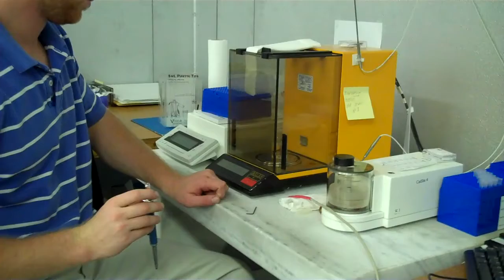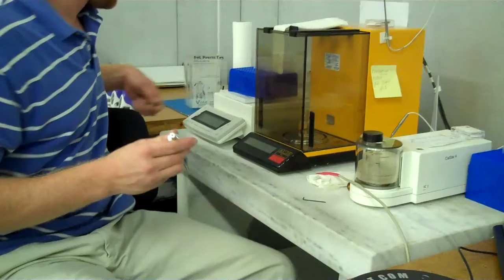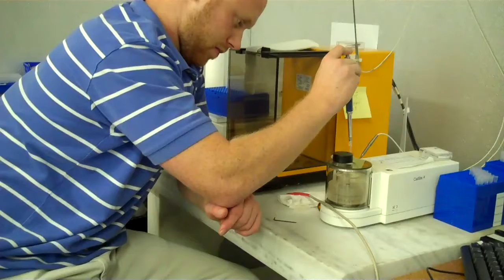Different brand pipettes have different methods to make these adjustments. For our MLA brand pipettes, an Allen key is inserted into the pipette plunger button. Turning the key clockwise increases the volume. Turning the key counterclockwise decreases the volume. Once the adjustments have been made, a new round of 4 shots are aspirated and dispensed to confirm that the pipette has been calibrated correctly.